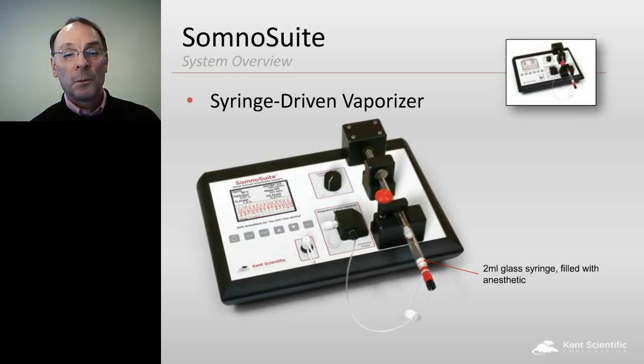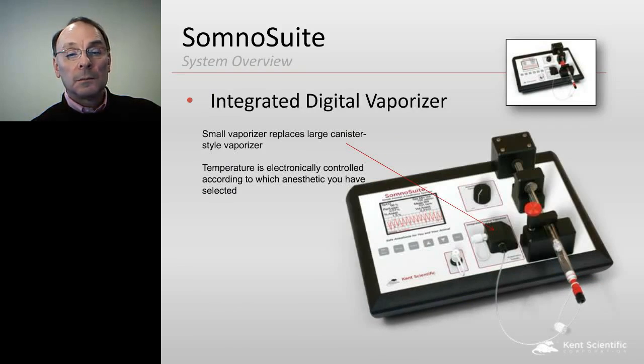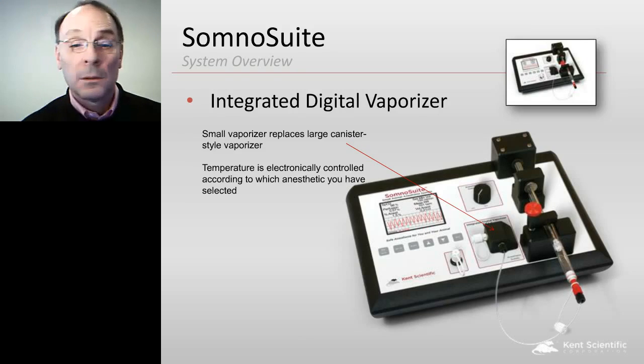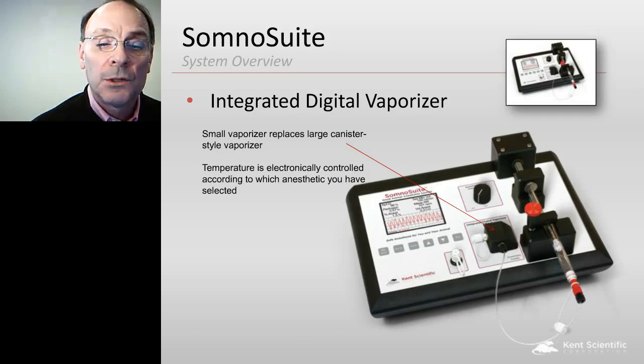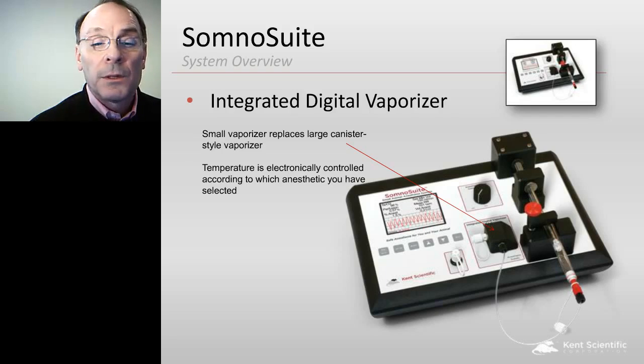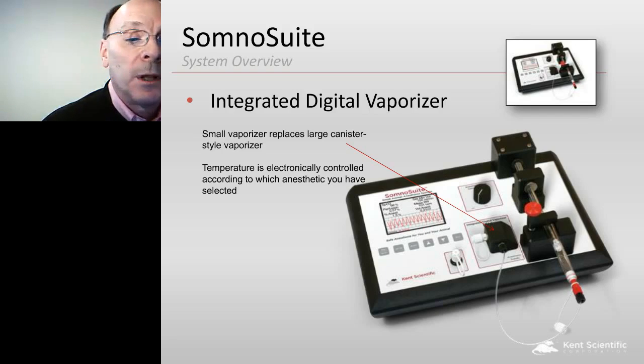anesthetic going into a warmed, heated vaporizer block. So the unit can take anywhere from 100 microliters up to a 10 milliliter gas-tight syringe, and the injection goes into the warming. We call it the integrated digital vaporizer, which injects the isoflurane or the sevoflurane into the warming block.